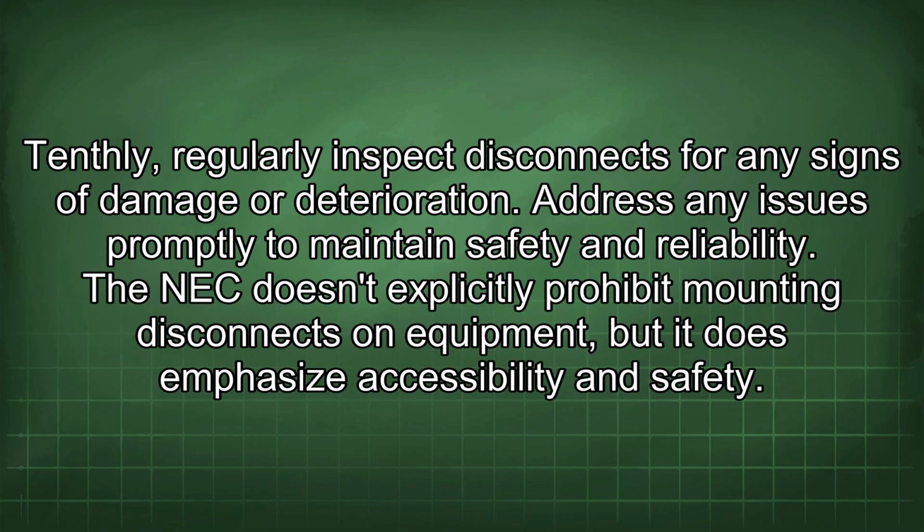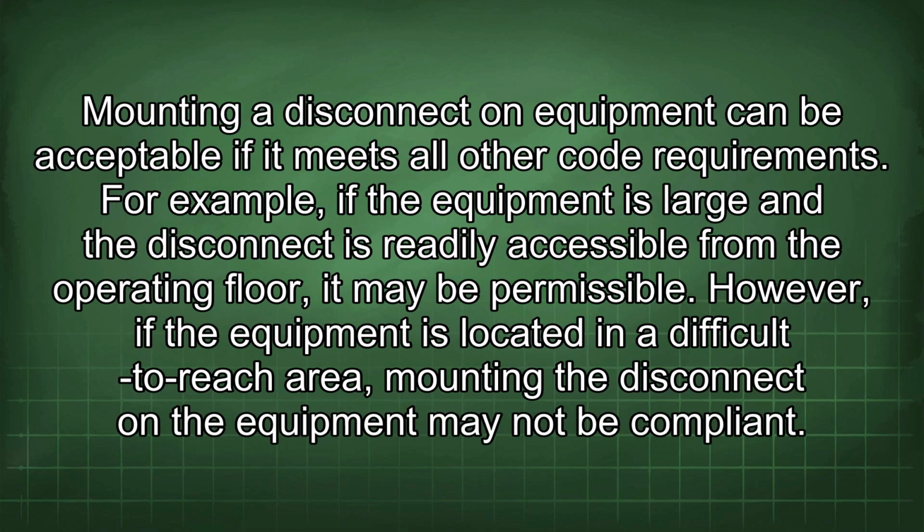The NEC doesn't explicitly prohibit mounting disconnects on equipment, but it does emphasize accessibility and safety. Mounting a disconnect on equipment can be acceptable if it meets all other code requirements. For example, if the equipment is large and the disconnect is readily accessible from the operating floor, it may be permissible.